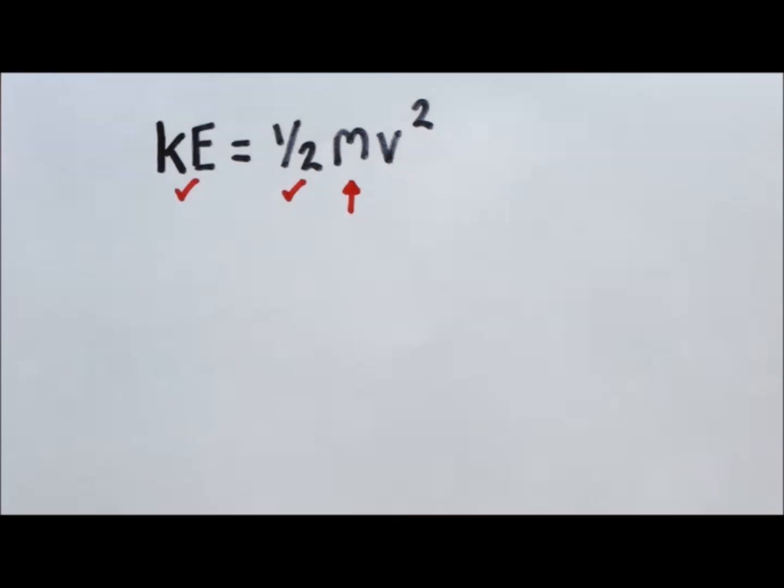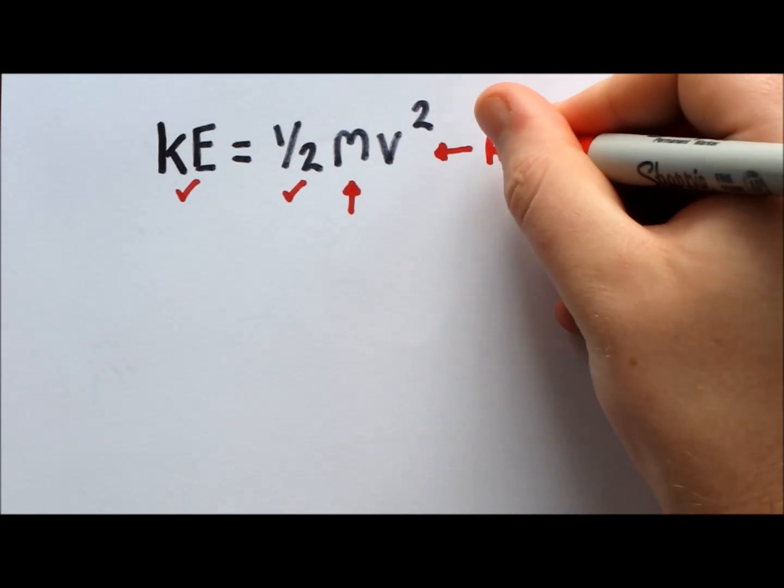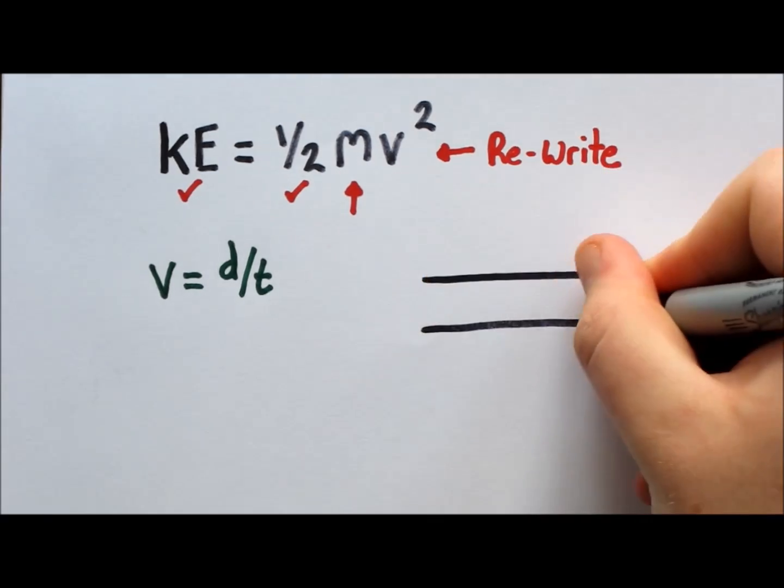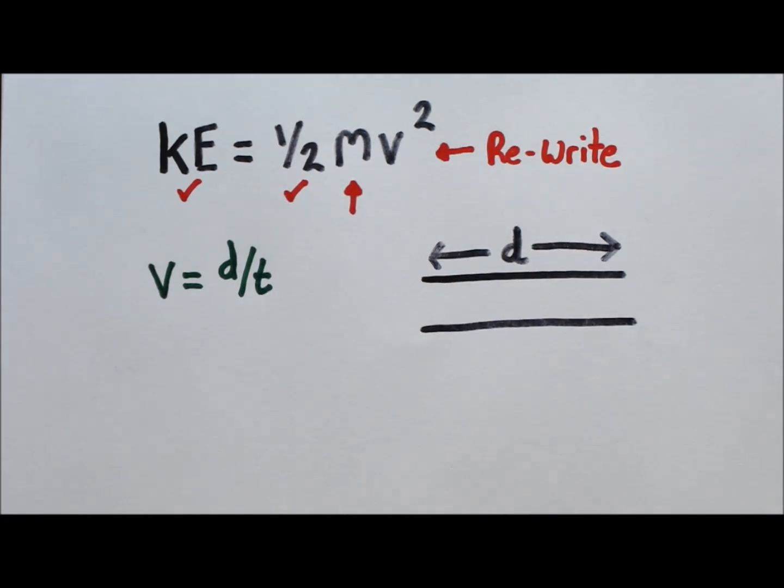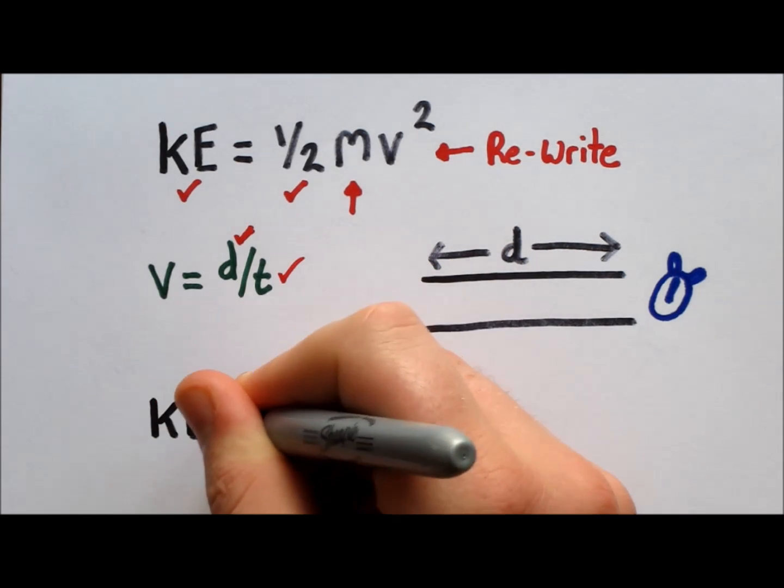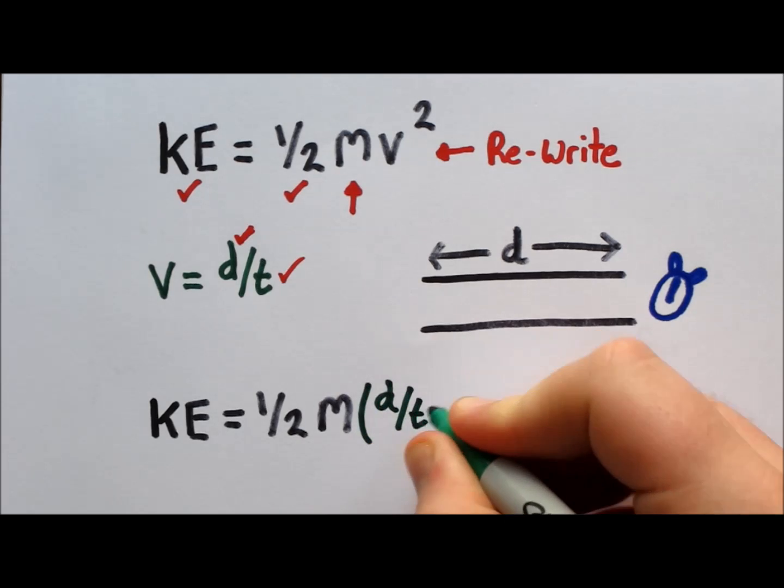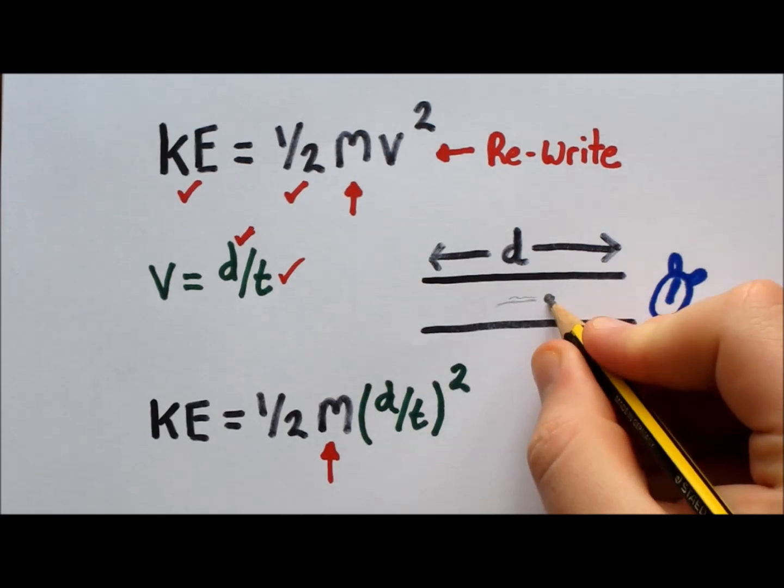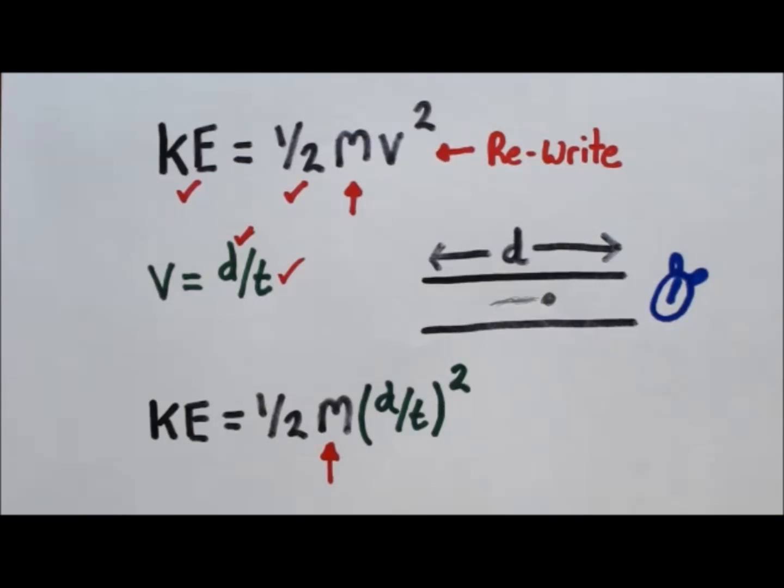One half is just a constant, and we are trying to find the mass. This just leaves velocity. We don't know the velocity, but we can rewrite it as distance over time, because the length of the flight tube is known, and we can accurately time how long it takes an ion to travel down the drift region to the detector. This means we can rewrite the equation, substituting d over t squared for v squared. This now just leaves the mass to be found. The only quantity being measured is the time, hence the name, time of flight.